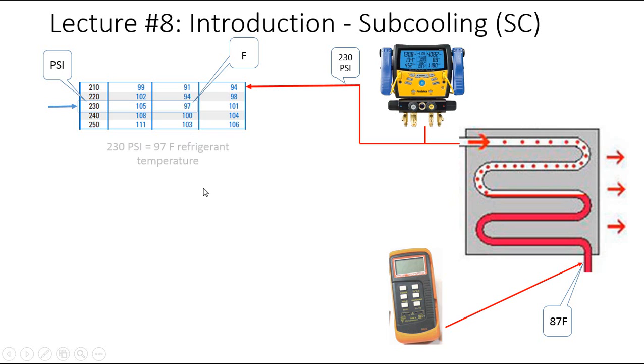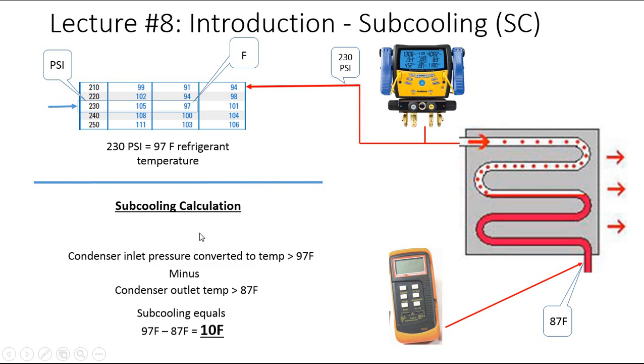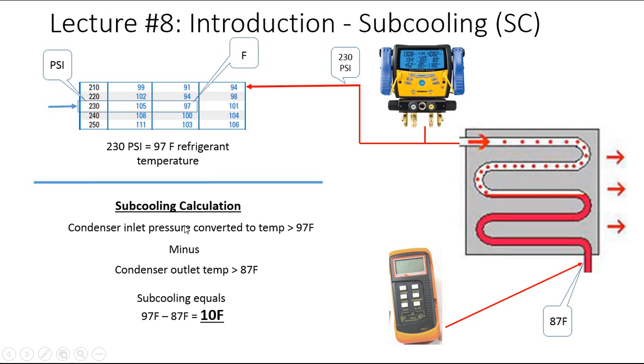You'll notice there's a difference here, right? Okay, so what we're going to do here is we're going to do our calculations. So how we do it is we take the condenser pressure and we're going to convert that to temperature, which we did up here, and we're going to subtract the physical line temperature from it right here. So in this case, 97 minus 87 is 10 degrees F. Now what is that, right? So if you remember in the last lecture, we said that subcooling is the additional heat removed from the liquefied refrigerant. So this makes perfect sense, right? So you have 97 degrees, that is the converted temperature of that refrigerant, but we've actually dropped it 10 additional degrees F, and that factor is our subcooling. So that tells us that our condenser has removed an additional 10 degrees after this state change has occurred, right? So that's pretty much it.